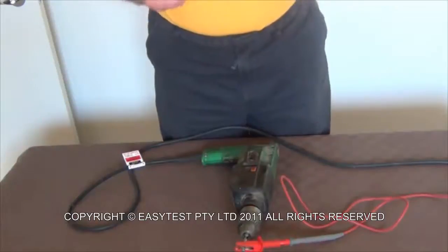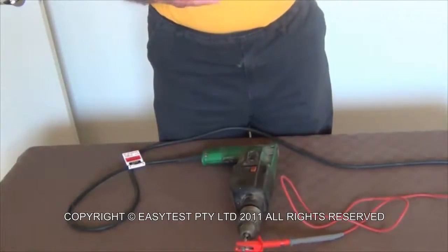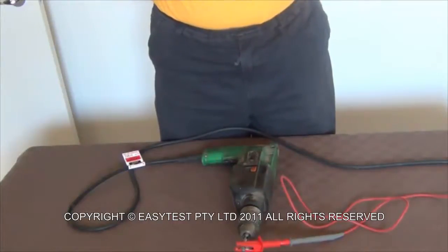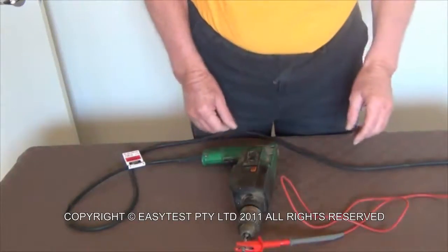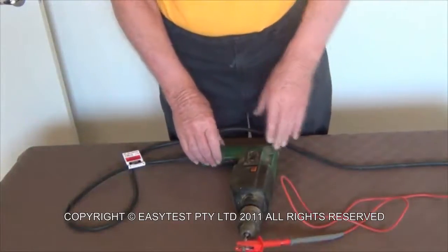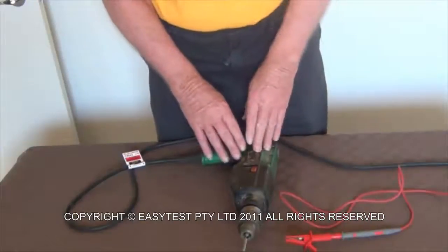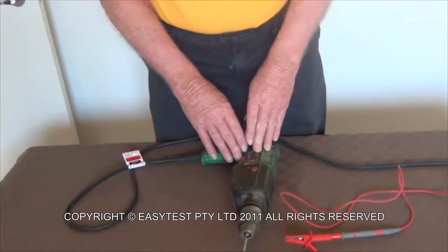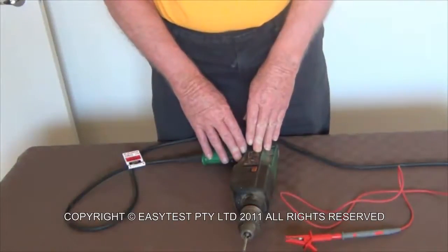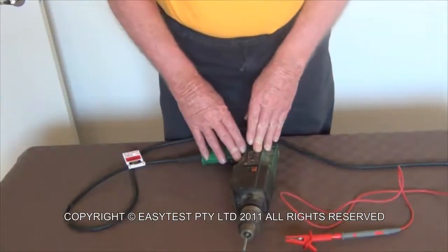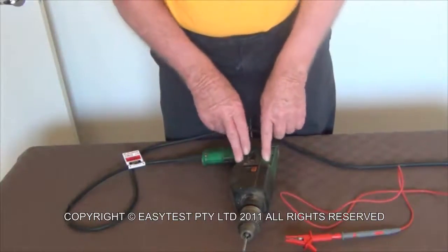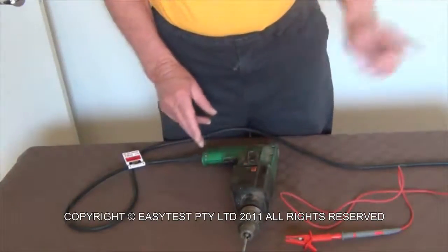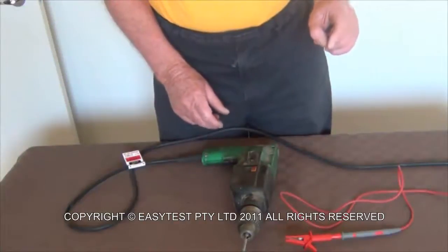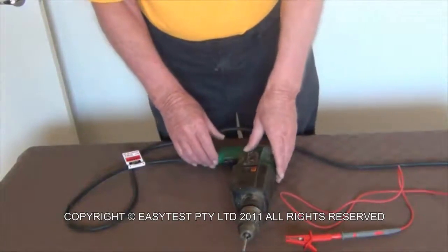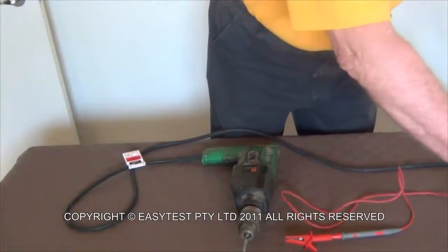Okay, notice that you first got a class 2 fail, which means the earth leakage exceeded 1 milliamp. You then got the message on there, dangerous fault, turn switch off. Now that is an additional safety feature that we've built into all of our range, where if you get earth leakage of greater than 9 milliamps, it shuts down. And that is exactly what happened here. The earth leakage exceeded 9 milliamps, so the tester shut itself down to protect you against any dangerous fault. That is, I think, pretty well unique in electrical testers.